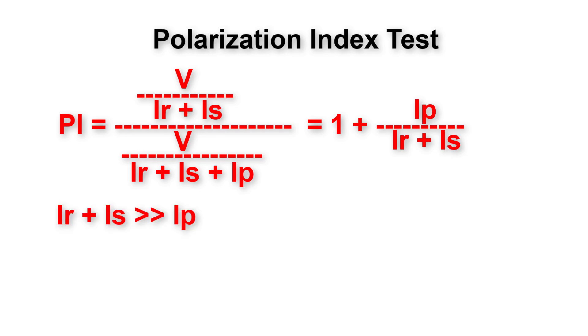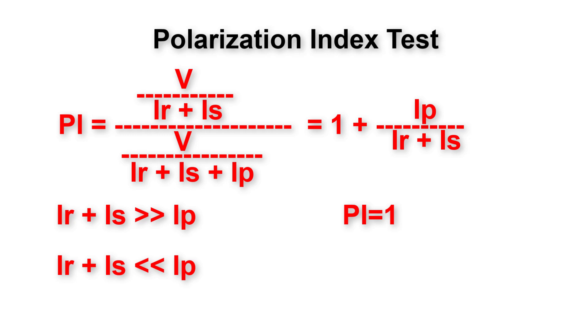When Ir + Is is much larger than Ip, the polarization index approaches 1, which is a poor value. If Ir or Is are large, this indicates unhealthiness of the insulation. Conversely, a high polarization current Ip compared to Ir and Is indicates a healthy insulator.